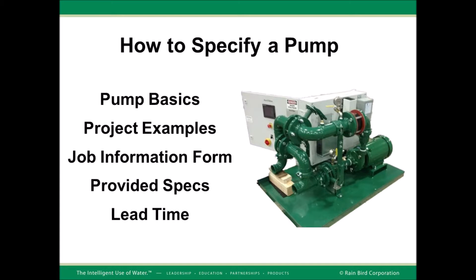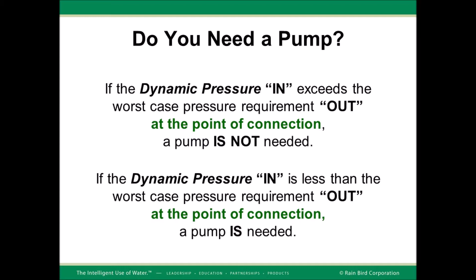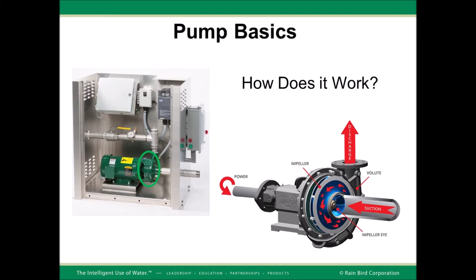Do you need a pump? If the dynamic pressure in exceeds the worst case pressure requirement out at the point of connection, a pump is not needed. But if the dynamic pressure in is less than the worst case pressure requirement out at the point of connection, a pump is needed. Pump basics. How does it work?